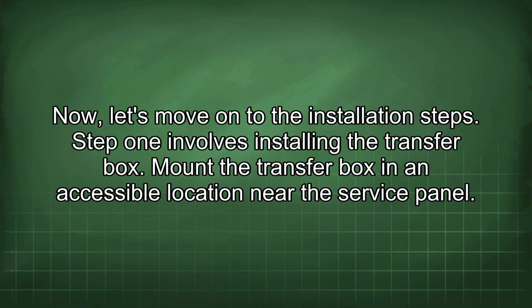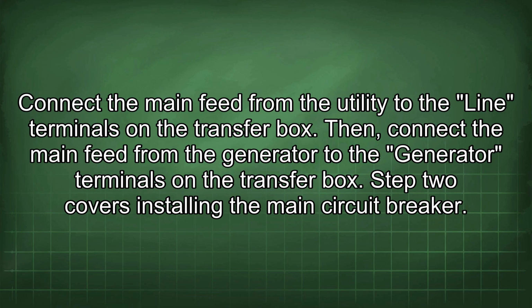Step 1 involves installing the transfer box. Mount the transfer box in an accessible location near the service panel. Connect the main feed from the utility to the line terminals on the transfer box. Then connect the main feed from the generator to the generator terminals on the transfer box.